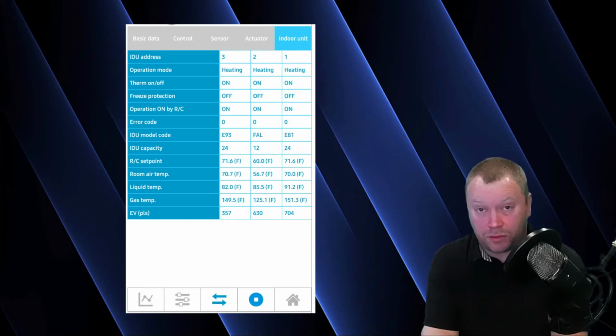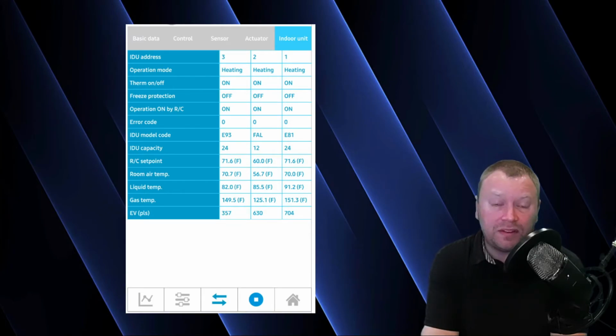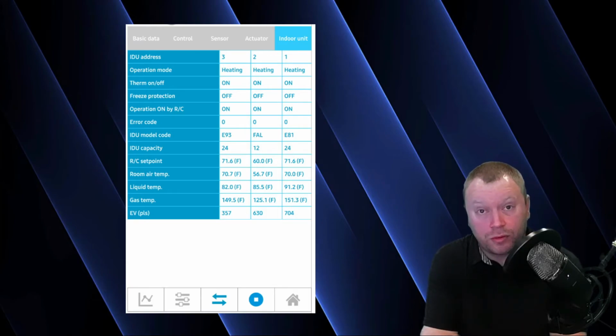Regardless of the amount of subcooling I have at this particular snapshot, I have 82, 85, and 91 degrees leaving my indoor units. And collectively, they're all going to mix by the time they get back to the outdoor unit because VRV systems have one line set that branches out to all the indoor units on the circuit. It's not individual line sets.